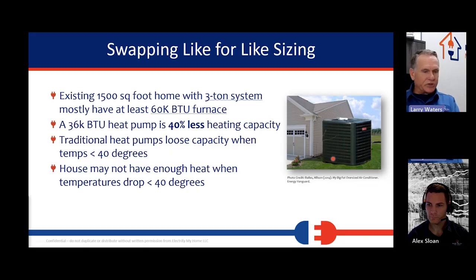So if we have an inverter system and we're keeping the house warm, it doesn't really matter because the house is already warm. So the unit just slows down or speeds up to take care of the load. It's when you let the house get cold and it drops below 40 degrees outside that these units won't work. That's when your customers get really mad.